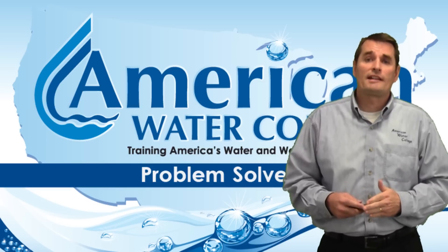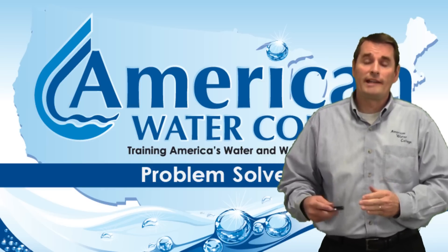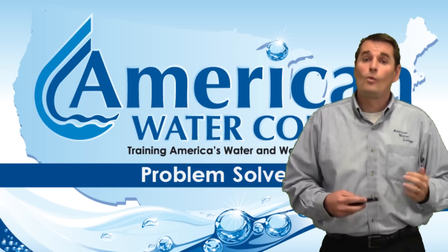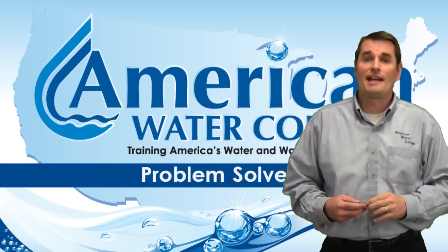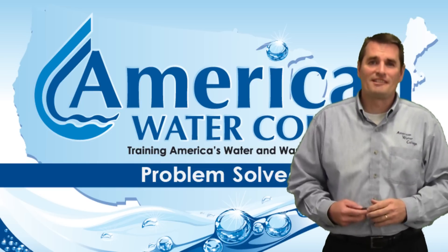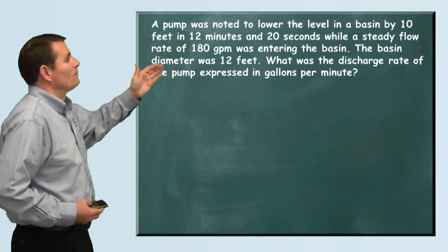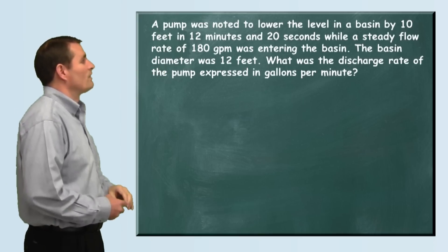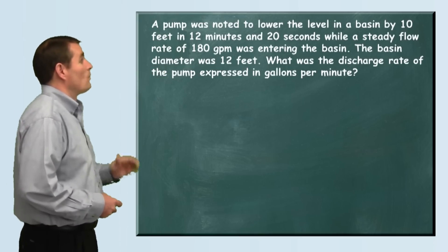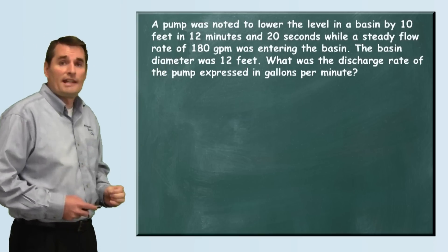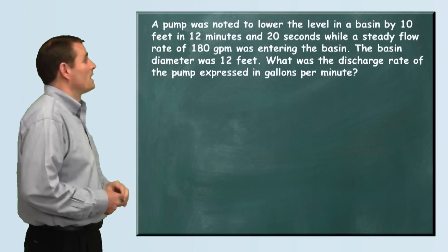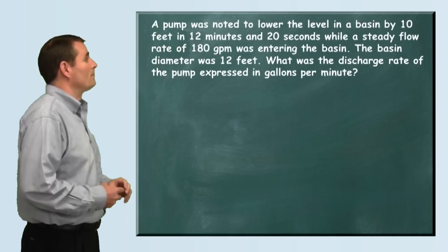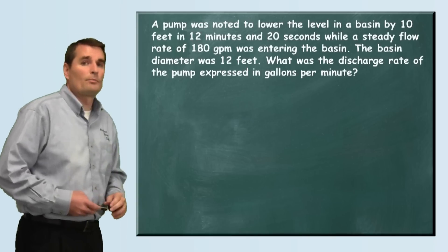In this problem we're going to learn how to calculate pump flow rate based on the rate at which a circular tank drops in level while we have flow coming into that tank. A pump was noted to lower the level in a basin by 10 feet in 12 minutes and 20 seconds while a steady flow rate of 180 gallons per minute was entering the basin. The basin diameter was 12 feet. What was the discharge rate of the pump expressed in gallons per minute?